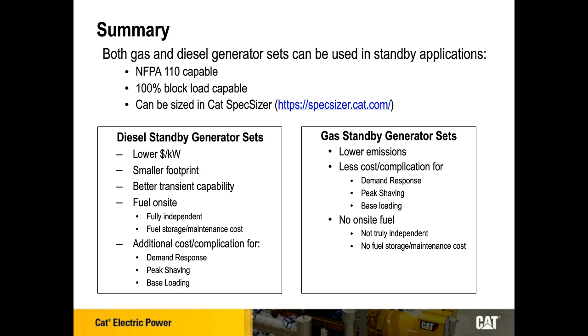Summarizing the differences between diesel and gas generator sets: diesel has a lower dollar per kW, which results in a smaller footprint, and better transient capability for picking up a starting motor. It also has fuel on site, so you can be fully independent of the utility, but you do have fuel storage cost and the maintenance of keeping that diesel fuel available. If you need a non-emergency application like demand response, peak shaving, or base loading, it adds a lot of complication and cost on the diesel side.